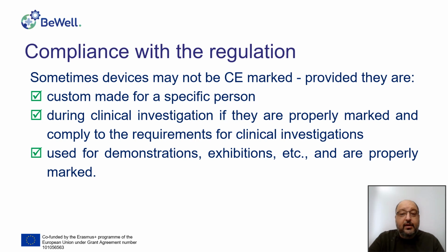In some cases, devices may not have a CE mark provided they meet the specific requirements. For example, if these devices are custom-made for a specific patient, or if they are put under clinical investigations and have clear marking for clinical investigation and comply with the regulation articles about clinical investigations. Also, devices for exhibitions, demonstrations, and so on, provided they are clearly marked that they are only for demonstrations and are not yet available.